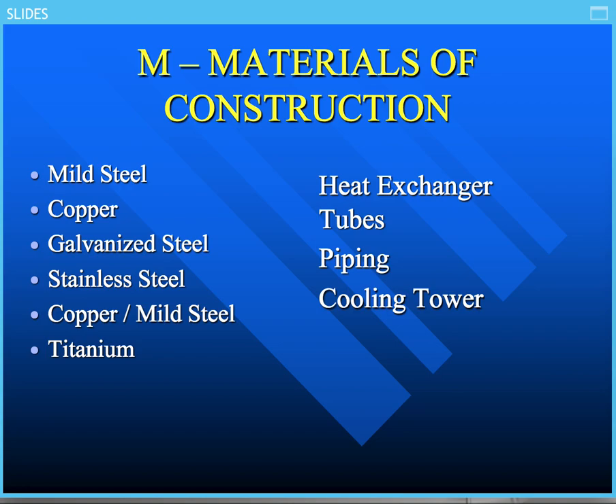You have to identify these. And don't forget these combinations where we have copper and mild steel, where we have galvanic couples. We want to make sure that we have things like that pretty much covered in our treatment program to be able to minimize or try to stop as much of that as we can, which is known as galvanic corrosion. And last, it would be nice to have titanium in many of the tubes of heat exchangers, but it's quite expensive. But it isn't very affordable. Titanium is resistant to most every type of thing that we can think of in regard to cooling water systems. So consequently, we have that.